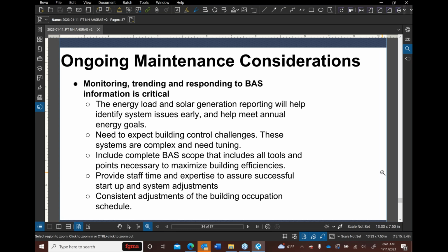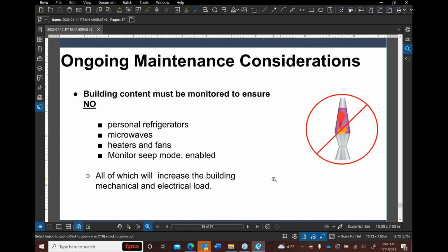And what about modes of operation? You have occupied, unoccupied. Do you have more modes? No. Jeff, do you know what's built into there? Yeah, typically we're occupied and unoccupied. What we've learned a little bit is, certainly we have allowed the system to offset its temperatures and reduce its temperature set points during off hours. We are studying very closely the energy impact of that. Sometimes we're finding that the spike in energy to get the building back up to temperature has been higher than we expected.